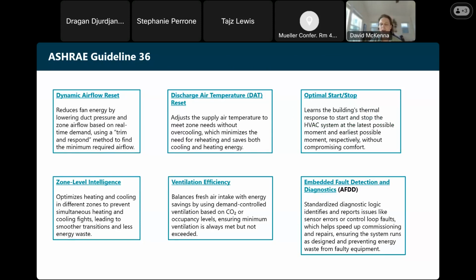Instead of providing a constant volume of outside air, like it would have historically been done, we can actually measure CO2 within the space. So that requires a CO2 sensor, the hardware within the space, and then obviously the software to interpret that. And so what we can do, again, this is just one example, is we can actually reduce the amount of outside air if we see that carbon dioxide level dropping. Basically, the fewer people in the building, we don't need to supply quite as much outside air. And in warm, humid climates like Central Texas, that can be a huge energy savings, because dehumidifying outside air is enormously energy intensive.